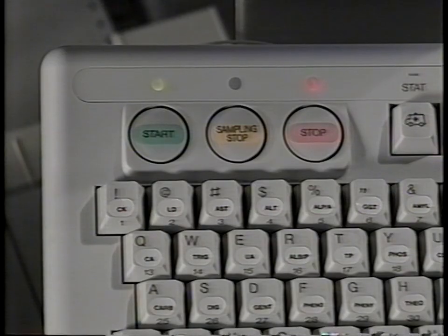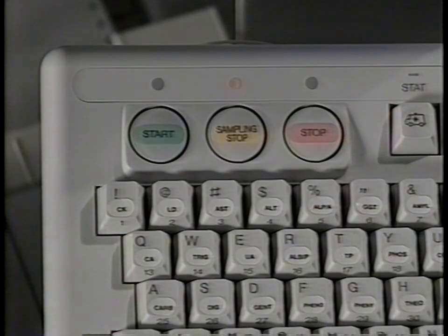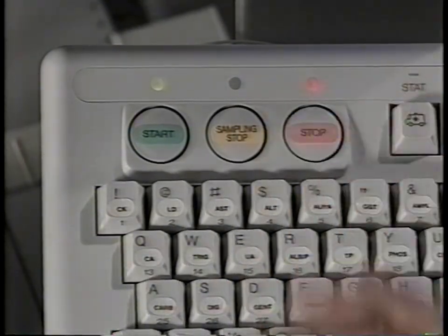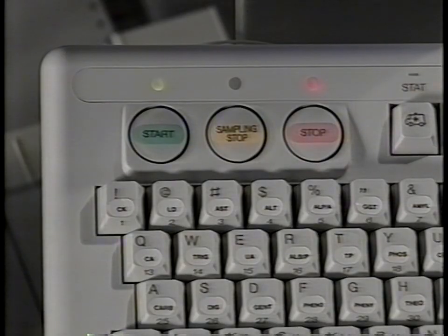The sampling stop key stops the sampling function at the end of the current sampling cycle. All the other functions related to tests already in process will continue until their results print out. When the instrument is in the sampling stop mode, the yellow light above the key is illuminated. When the stop key is pressed during operation, any samples which have been identified but do not have results available will require reprocessing. The stop key can also be used to terminate certain mechanism testing functions.